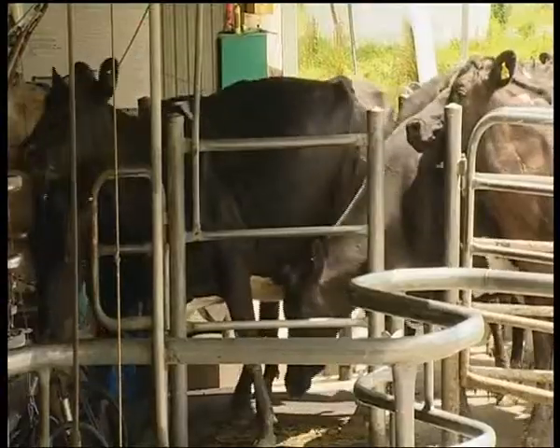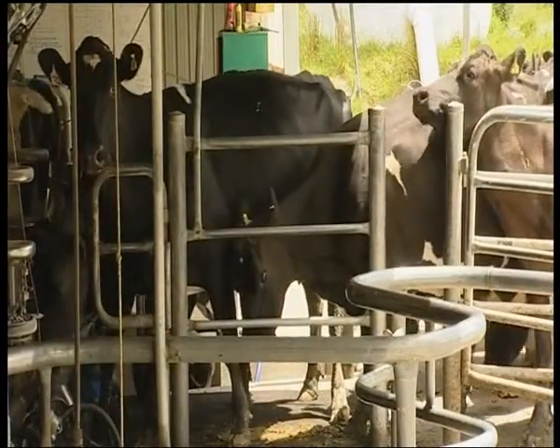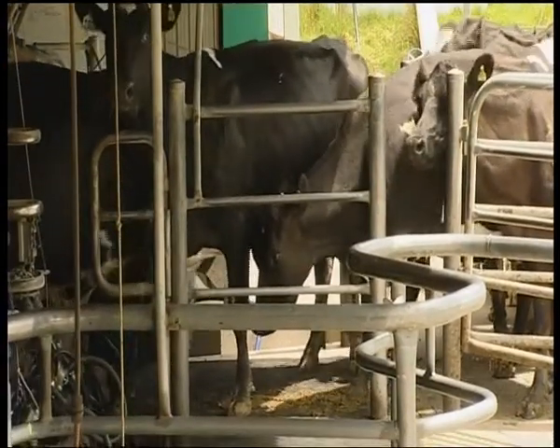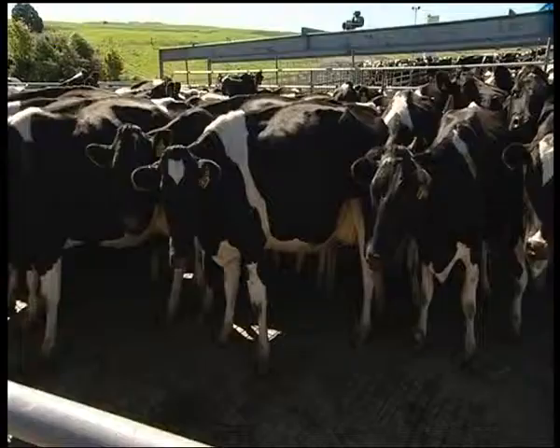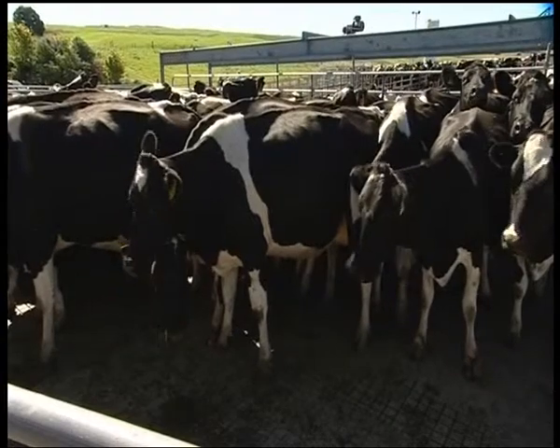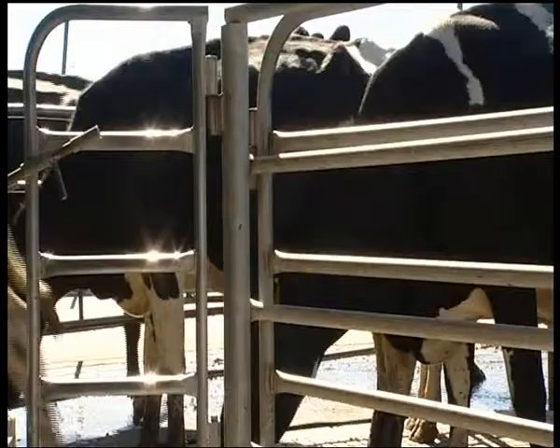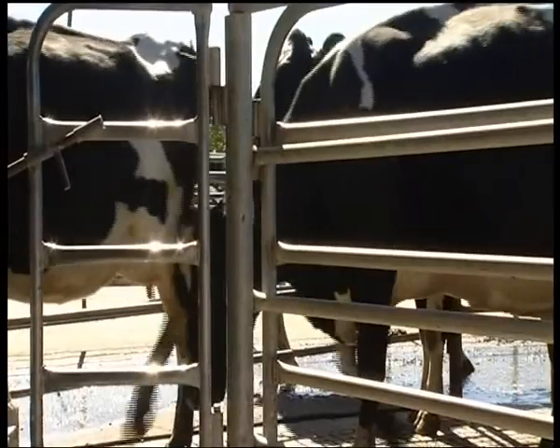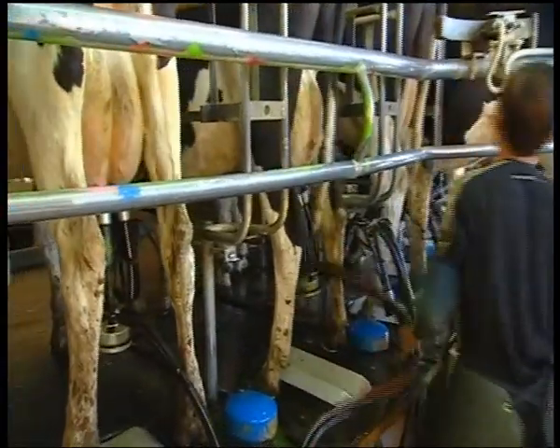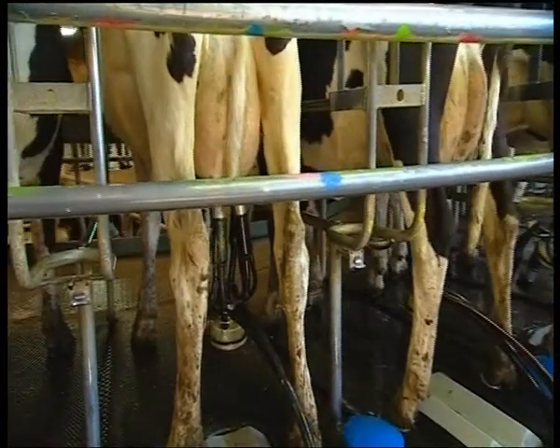Stray voltage is actually a very broad term. It's probably a false term. It really means the effect on cows from voltage-related equipment, and it can be in many forms. The basic form is what we call neutral-related stray voltage, and that's where a voltage at the switchboard can't get back to the transformer, and goes via the steelwork and therefore by the cows back to the transformer. A cow is 15 times more sensitive at least than a human to stray voltage. And if the cow can feel the stray voltage, she will retain her milk. And when she retains milk, then you get the bugs working, and then up goes your somatic cell count, ultimately mastitis.